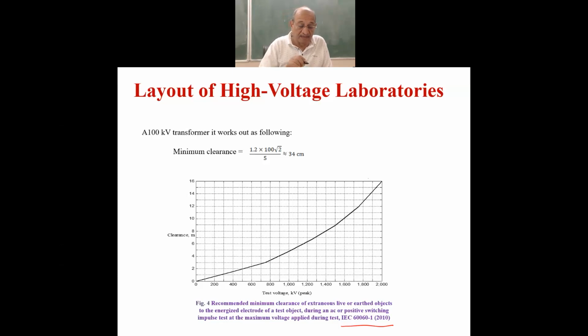So this is the clearance in meters given here, and this is the test voltage in peak. For clearance, you would always need to consider the peak magnitude of the voltage. That comes basically for AC power frequency. For DC, it is always the peak. For impulse voltages, it is only the peak which is under consideration. So for test voltages, in kV peak, this has been recommended. This graph has been recommended by IEC.